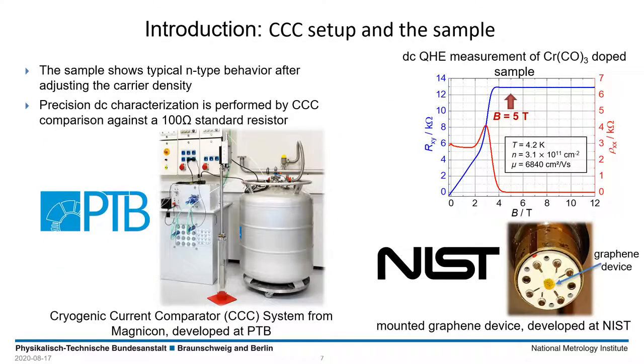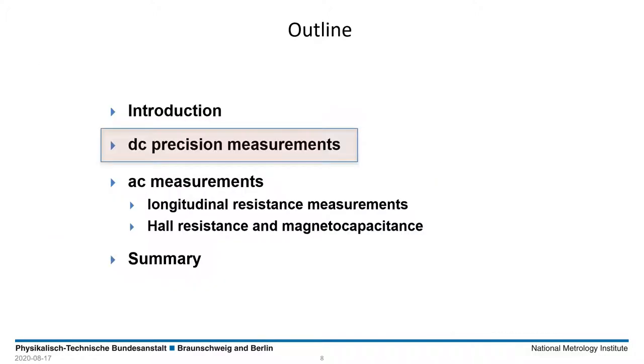On the lower left side, you see the mounted graphene device from NIST that is in all cases adjusted to an N-type carrier density in the lower range of 10^11 per square centimeter using the described doping technique. For DC precision characterization, we used our CCC resistance bridge from Magnicon to compare the QHR device to a 100 ohm standard resistor. This brings me to the results of the DC precision measurements.